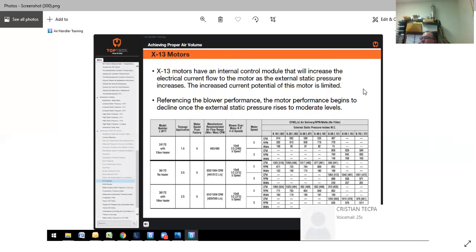X13s have an internal control module that will increase the electrical current flow to the motor as the external static pressure increases. This increased current potential of the motor is limited. So you can push these motors pretty far, but once you push them to a certain point, they'll fold back, or they'll start reducing speed to protect themselves. They can actually cut in half, to where you think you're at a certain RPM or speed, but it will not let you operate there, and it'll cut it in half.